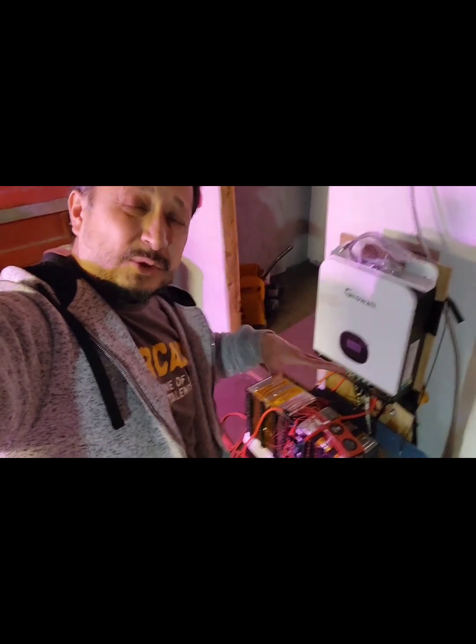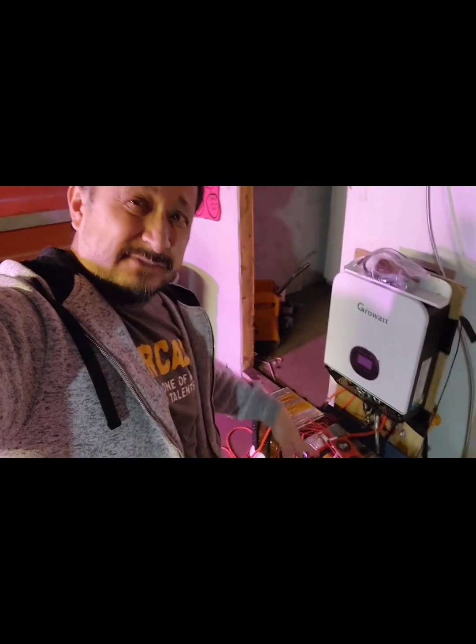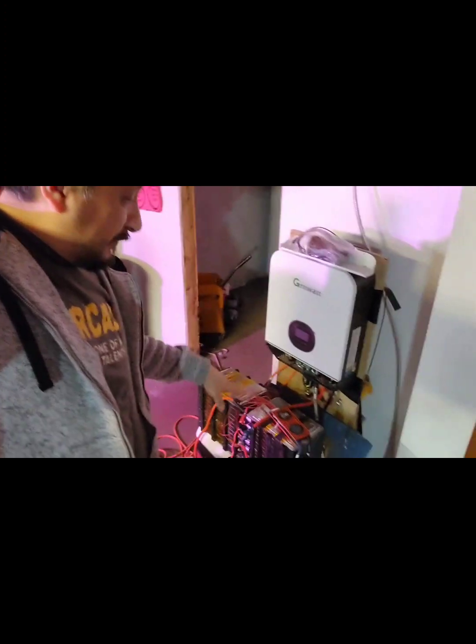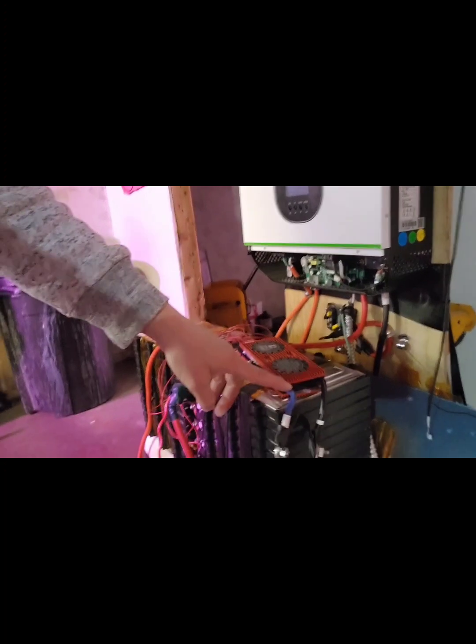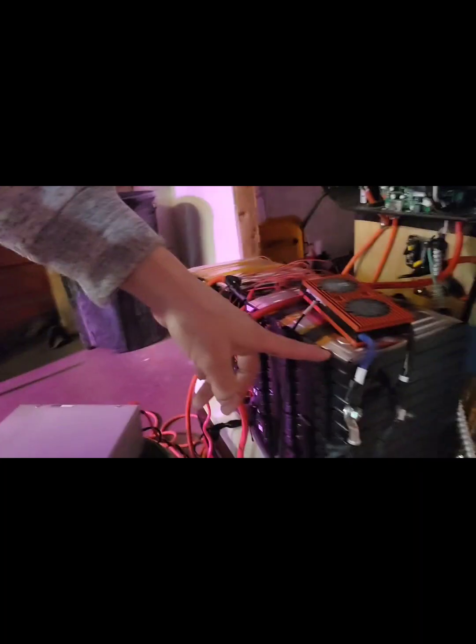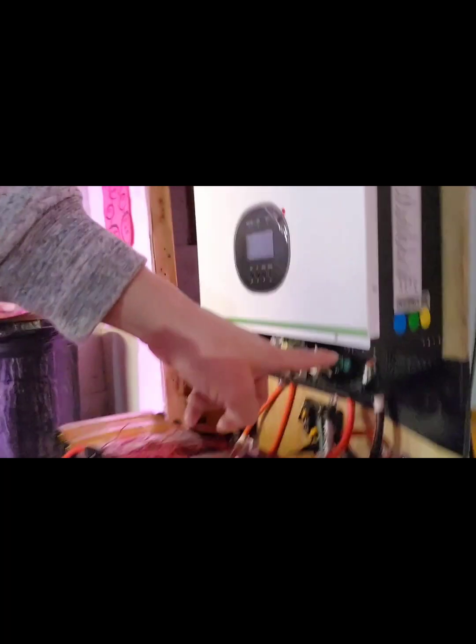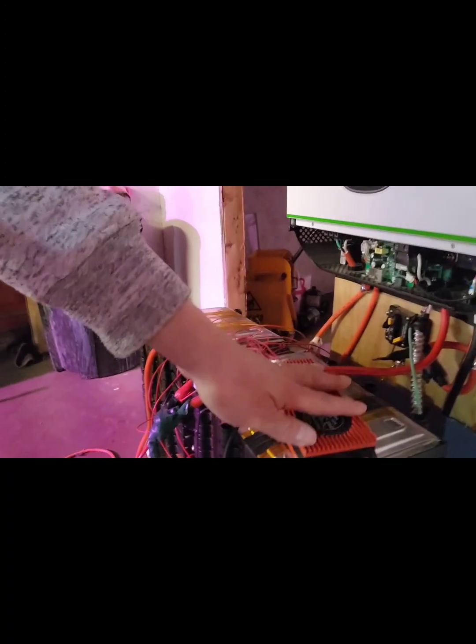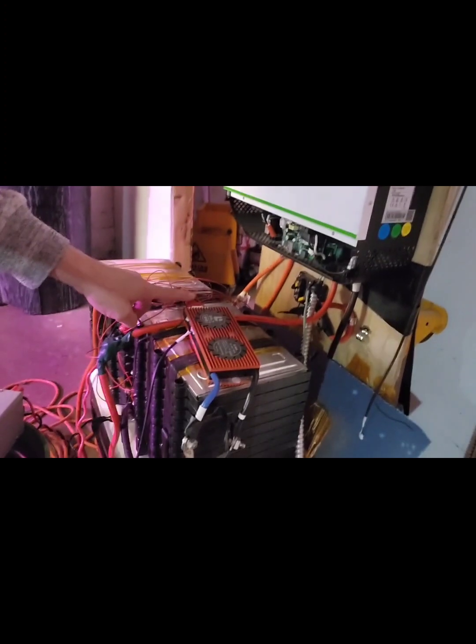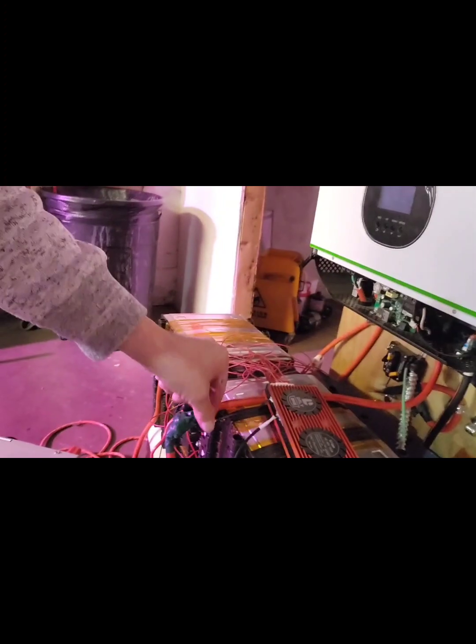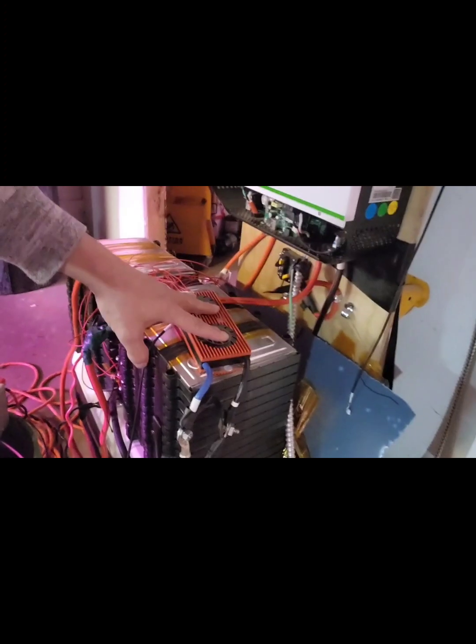What this is supposed to do is, as it's charging, actively make sure the battery doesn't go up to 4.2 volts on each individual cell, and keep them all balanced together. The blue line is connected to the main output of the battery pack, and this black one goes into the Growatt inverter. It monitors each cell, and it even has a temperature sensor. If there's something wrong, it disconnects the negative, shuts the battery down, and shuts your system down.